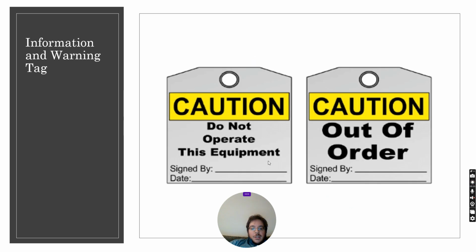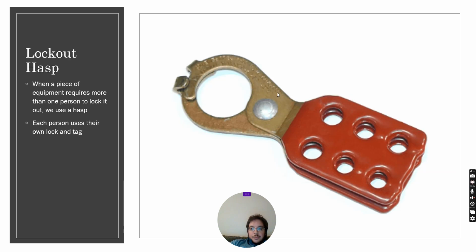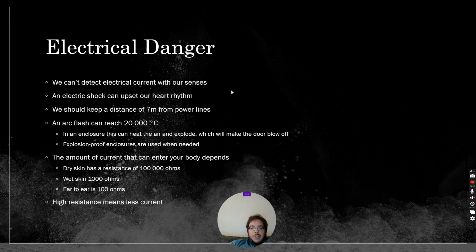Now, on top of that, you need to have a warning tag, so you can put the warning tag on the physical equipment. That way, if somebody comes up to the equipment and says, "Why isn't this thing on?" then they say, "Oh, it's not on because somebody's working on it." So then they won't go to the breaker and try to turn it on, because people are dumb. They'll see this thing, and if it's not on, they might try to somehow get this equipment turned on, or even cut the tag off.